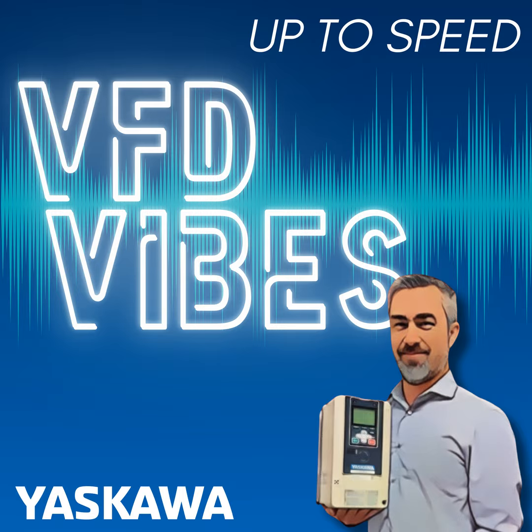So using what they call resistance grounding minimizes the current that can flow in a line-to-ground fault. And in fact, the most common kind of resistance grounding is what they call high-resistance ground. And the resistance is usually sized, the ohms of the resistor are sized, to keep the ground current less than about 10 amps. So I assume that resistor sits between the neutral then and the ground. That's correct. And this eliminates most common arc flash hazards.